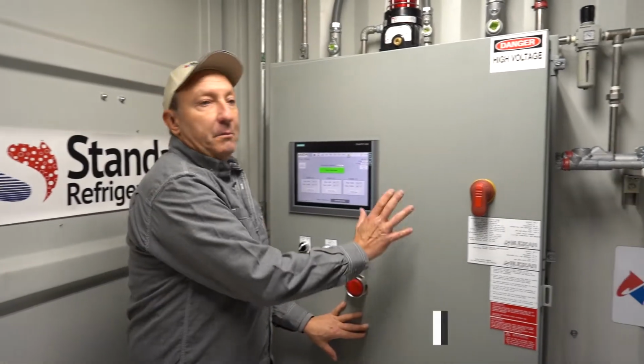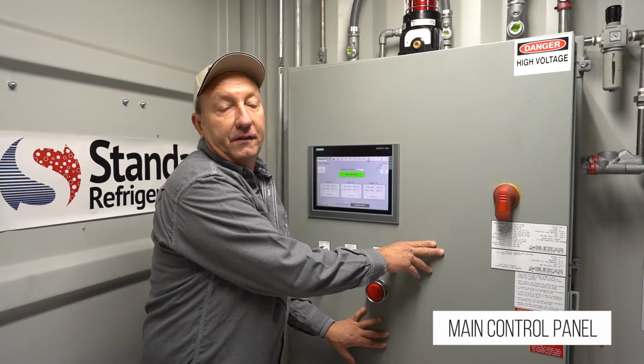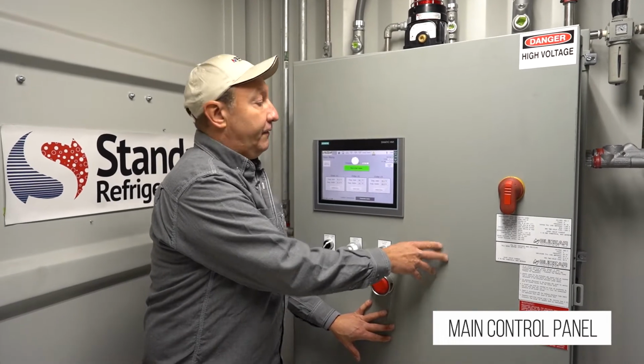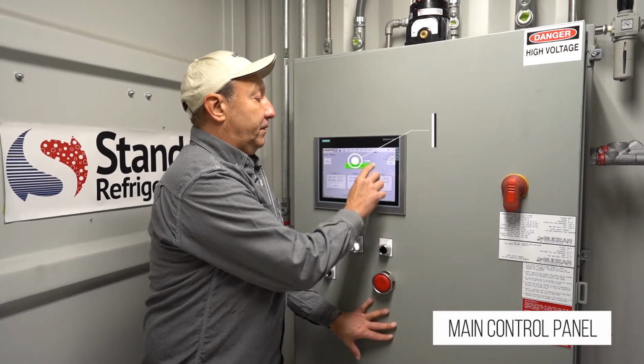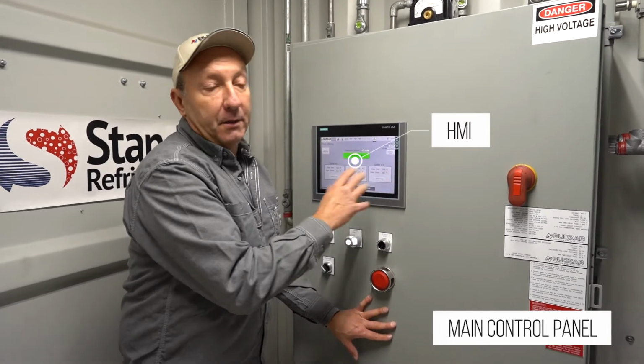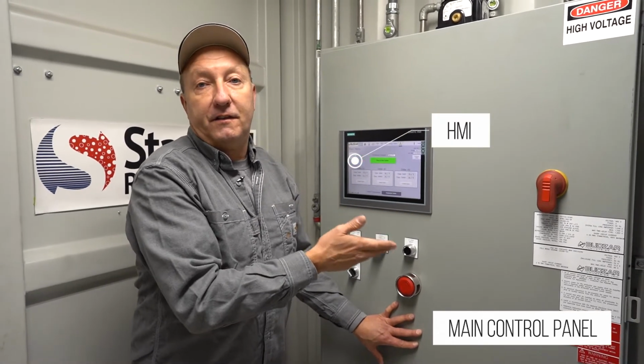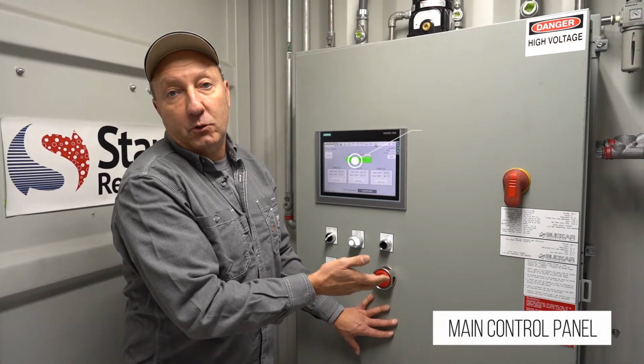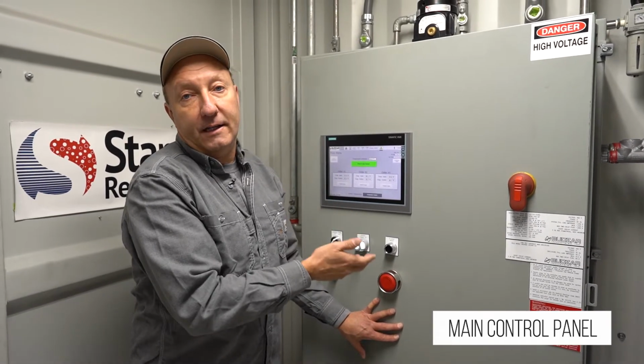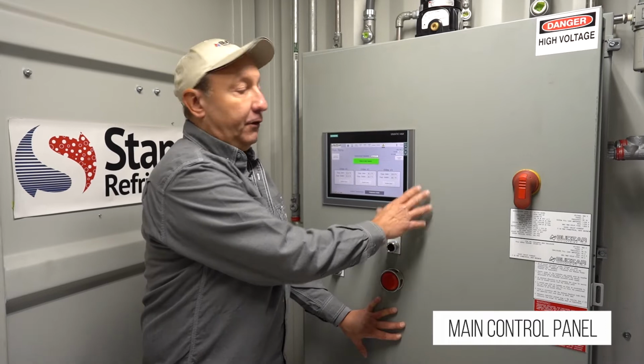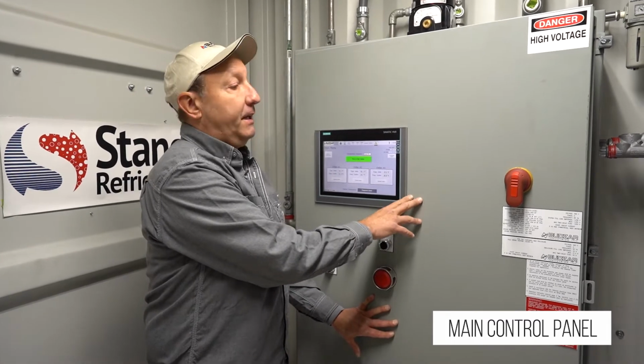Okay, this is the main control panel for the entire system. In this enclosure we have our HMI, which is our touchscreen panel where we can maneuver and see the status of the system. We could operate things in manual control. We could access the PID tuning blocks. It's very versatile and very useful for this application.